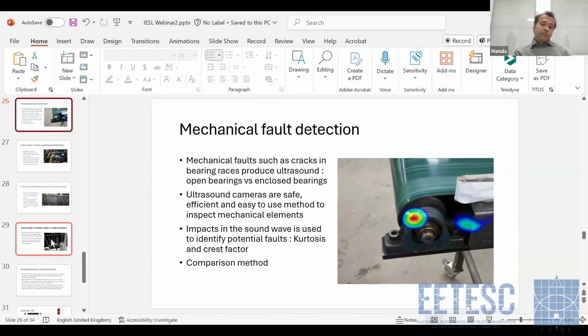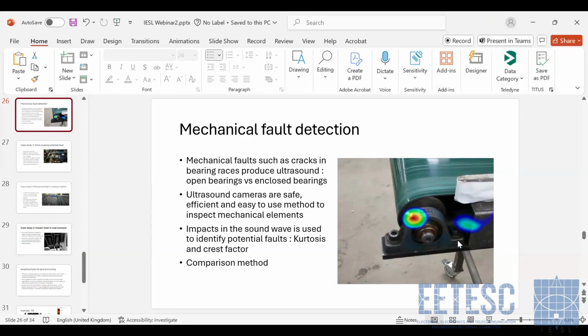Yeah. There are sealed bearings which are enclosed inside motors. So in those cases, it is not practical to use airborne ultrasound. But this kind of open bearings, which is open to the environment, in some cases can be detected. And those are static, is it? They're not moving. Actually, the bearing is rotating, but this outer part, the bearing housing, is stationary. So this is a fault in the housing, is it?